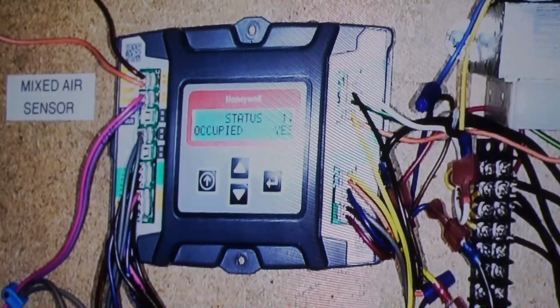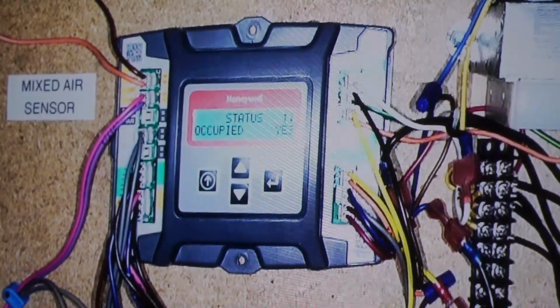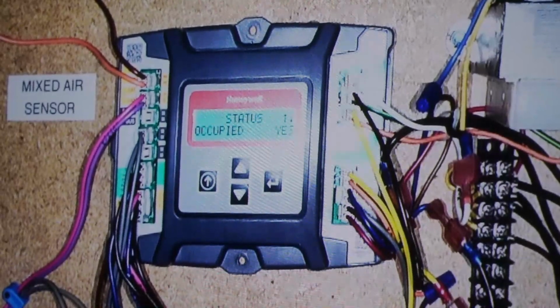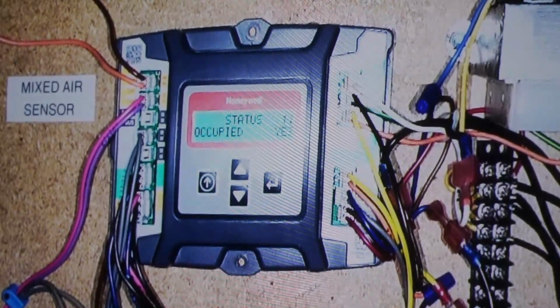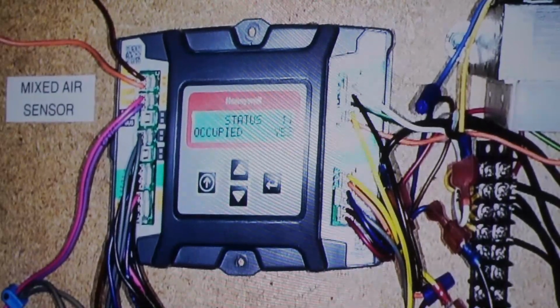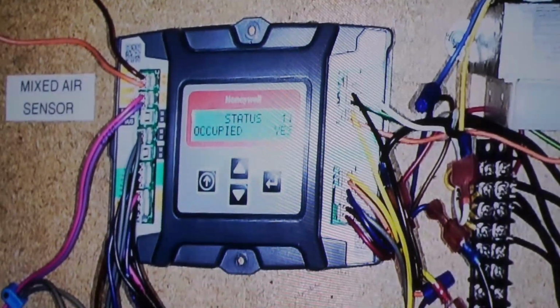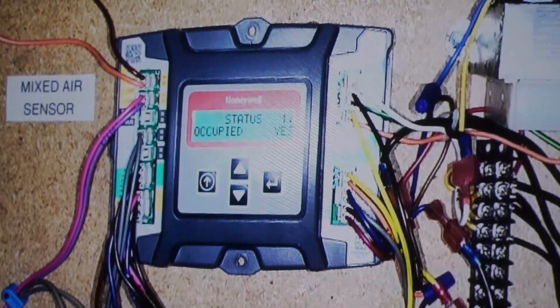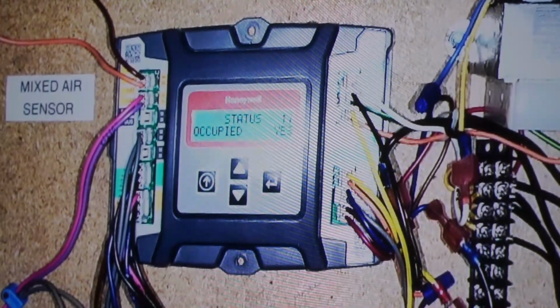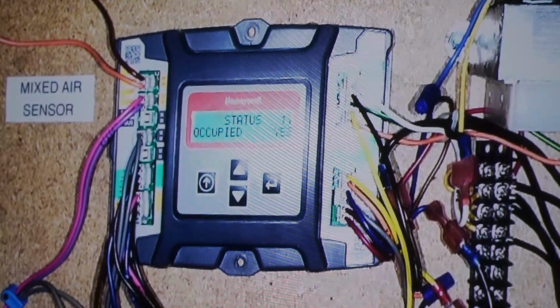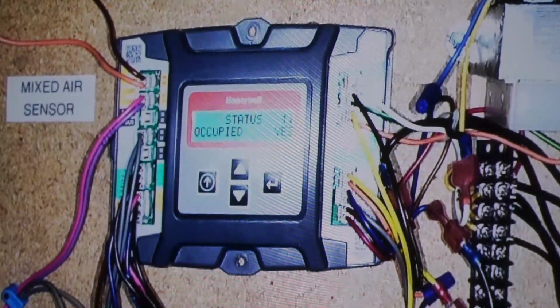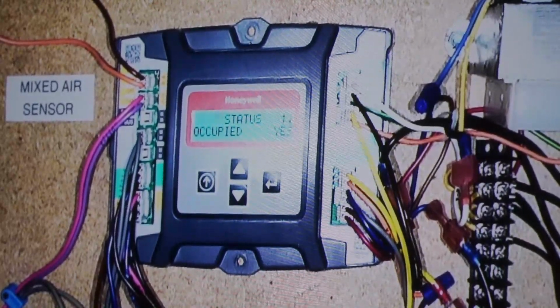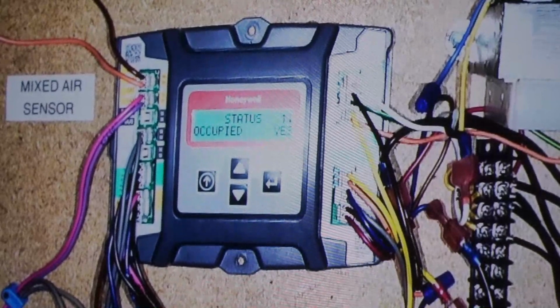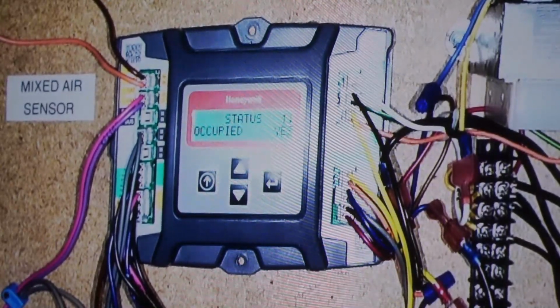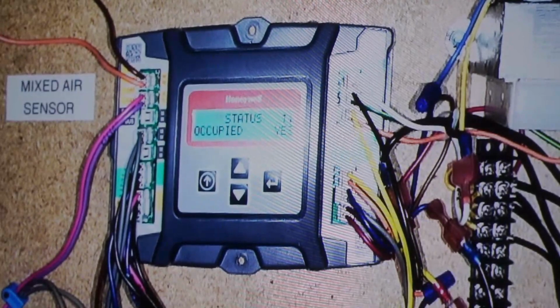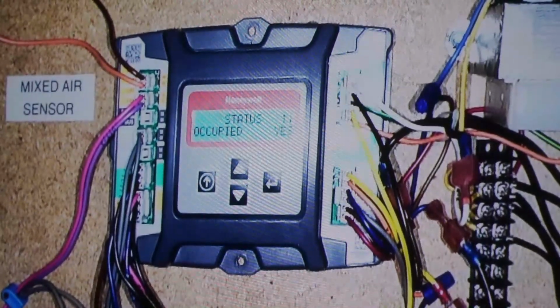It can also be, every Carrier unit, Bryant, Carrier, ICP, comes with factory wired. If you've got power on G, you're occupied. So, constant fan during the day, remember we talked about that for ventilation air? Or, if I've got a call for heat or cool. So what could happen at night if I don't change the wiring, which 99% of the people don't do? I get a call for heating in the middle of the night because it's freaking cold outside. I'm bringing in outside air.